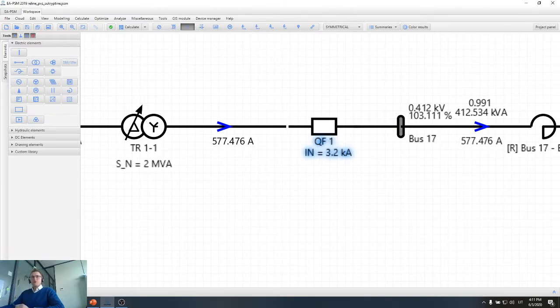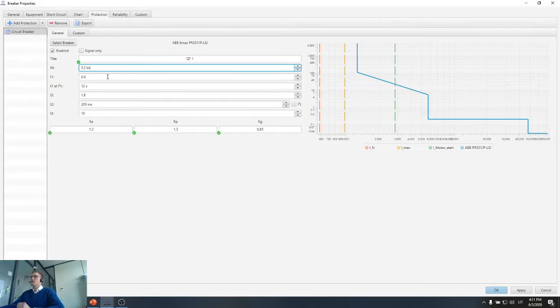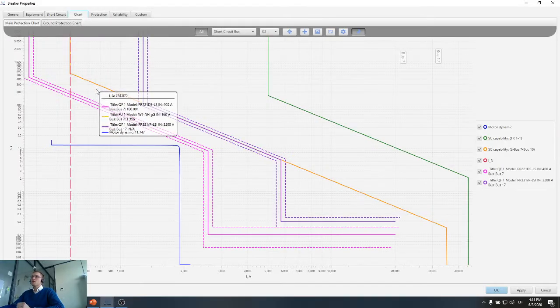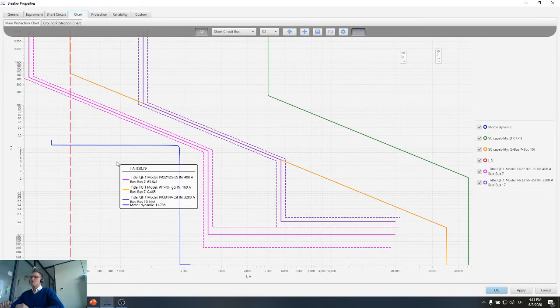And then there was a question about standby earth fault protection. So I will talk about the earth fault protection. What is the time margin for the coordination? Basically, the recommended time margin should be around 150 milliseconds.